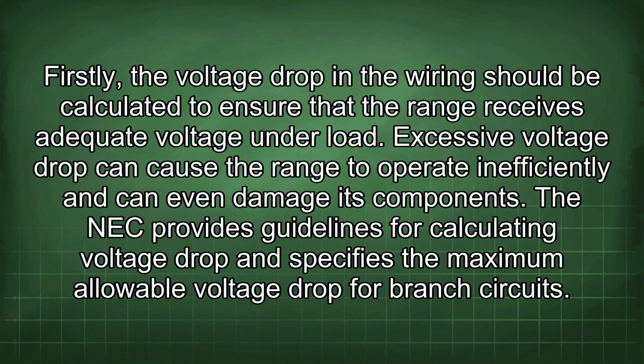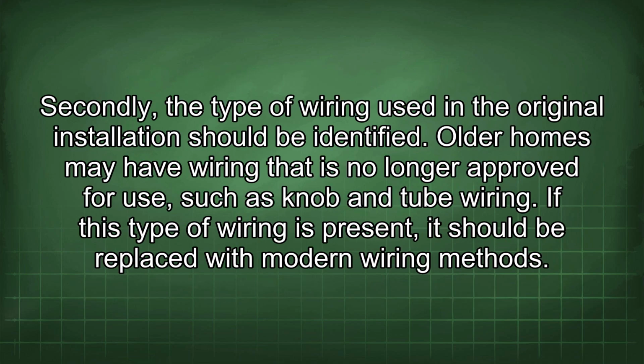Firstly, the voltage drop in the wiring should be calculated to ensure that the range receives adequate voltage under load. Excessive voltage drop can cause the range to operate inefficiently and can even damage its components. The NEC provides guidelines for calculating voltage drop and specifies the maximum allowable voltage drop for branch circuits. Secondly, the type of wiring used in the original installation should be identified. Older homes may have wiring that is no longer approved for use, such as knob and tube wiring. If this type of wiring is present, it should be replaced with modern wiring methods.